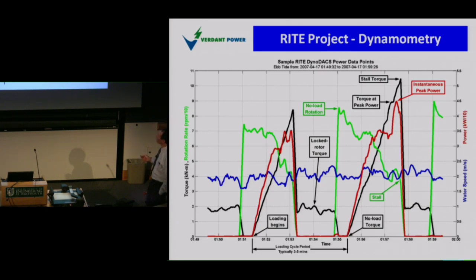So what we would do is load the turbine — the black line here is the torque. We would apply air pressure to the brake, which could be done manually or automatically. As you go up, the power goes up — that's the red line. The rotation rate goes down until you stall it, and then you do it all over again, so you can see what's going on.